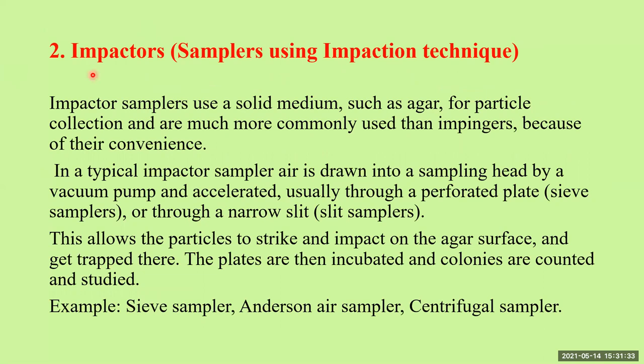Another type of active air sampler is the impactor. Impactor samplers use a solid medium like agar for particle collection and are much more commonly used than impingers because of their convenience. In a typical impactor sampler, air is drawn into a sampling head by a vacuum pump and that volume of air is accelerated through a perforated plate — also called a sieve sampler — or through a narrow slit, called a slit sampler.